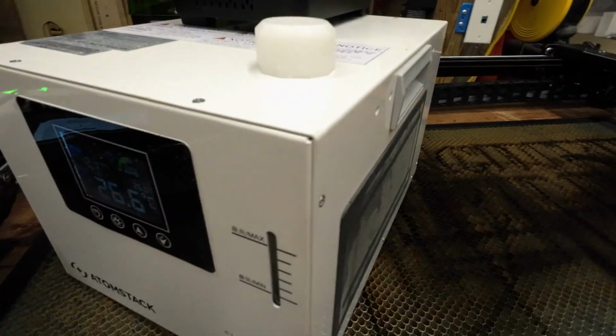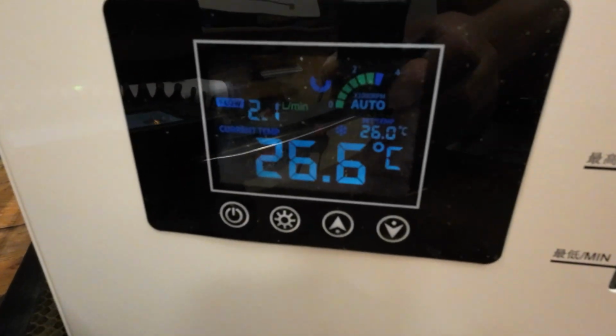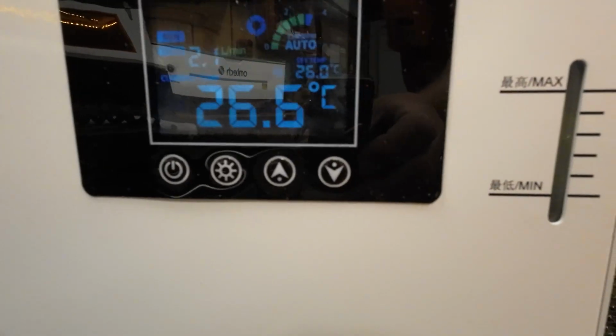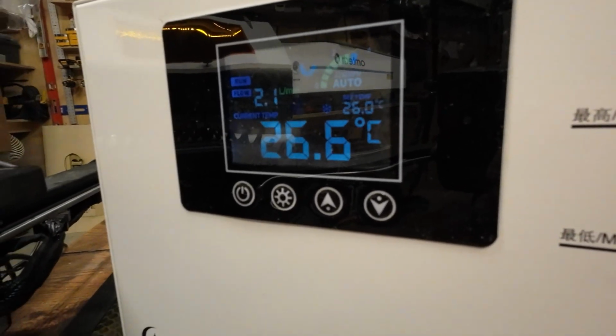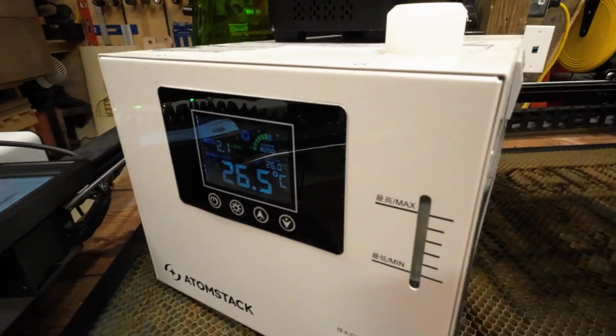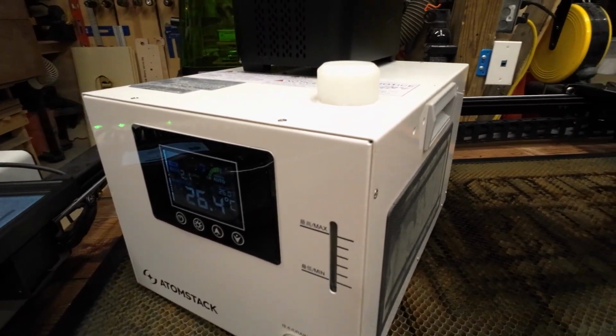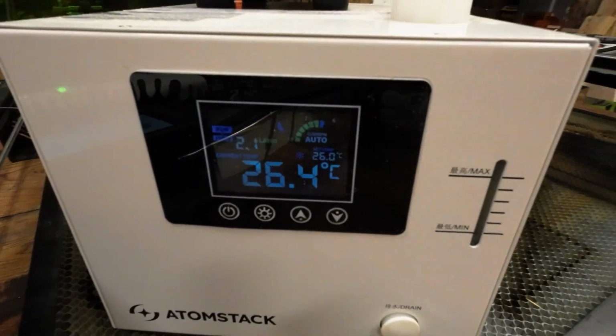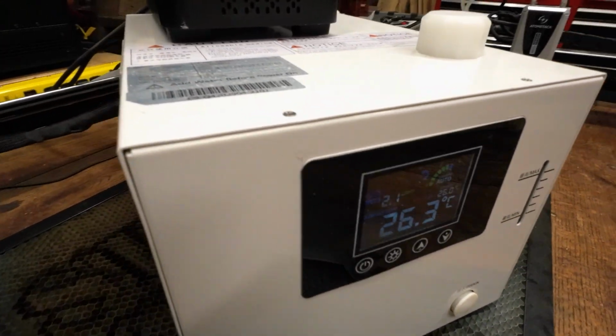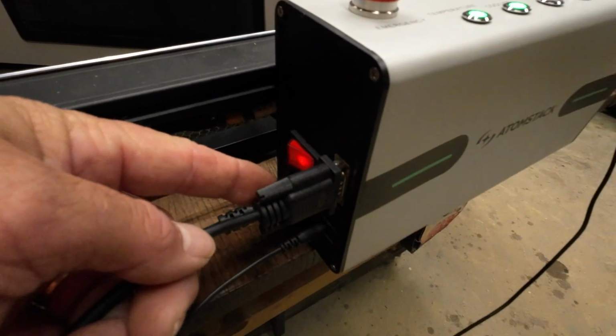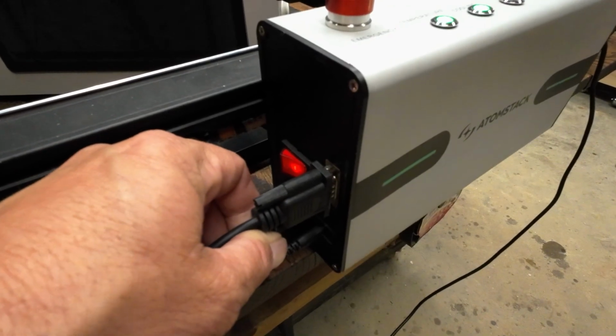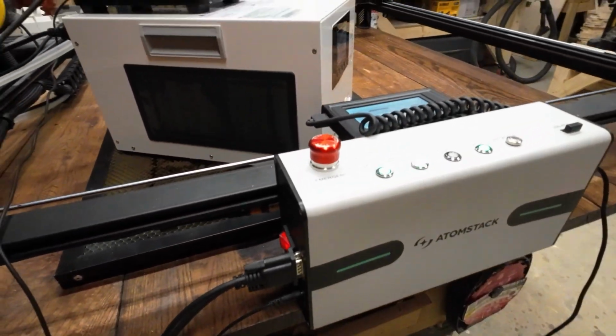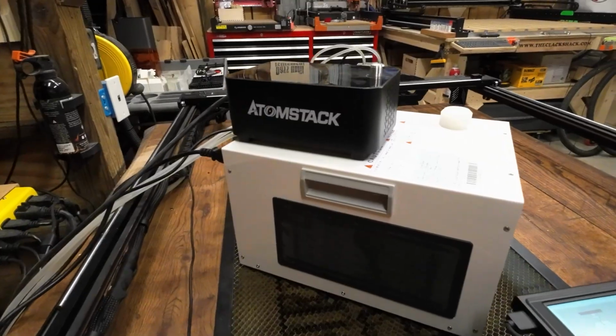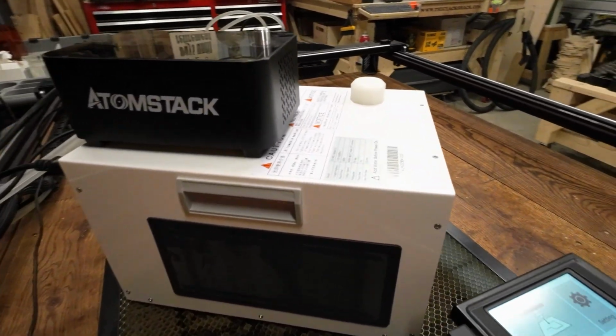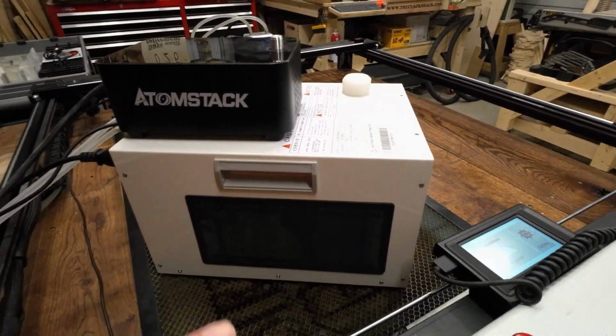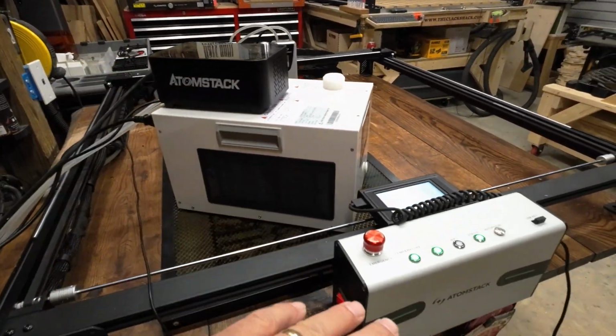But you can see here the control panel on the front of the chiller. It does have a readout with lots of information there, but the machine will give you an audible alert. It will let you know if something's going wrong with the chiller. It does communicate through this serial connector here with the laser, and you can see a data stream if you open up the command window in Lightburn, or if you go to their view tool in Atomstack software, you can see the communications of the status of the chiller with the laser.